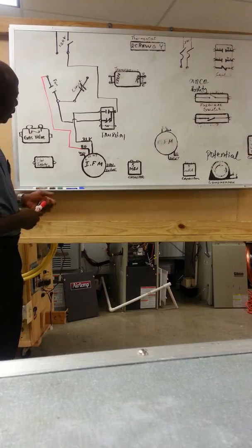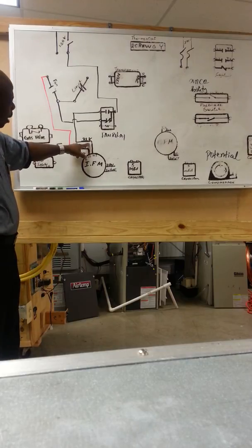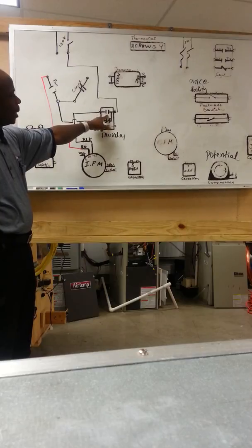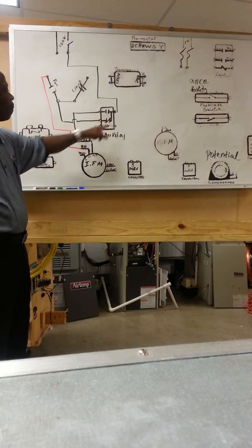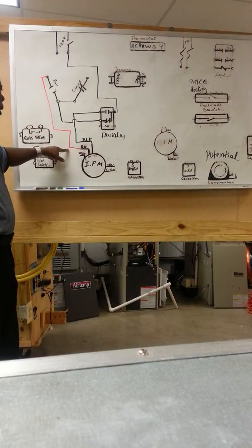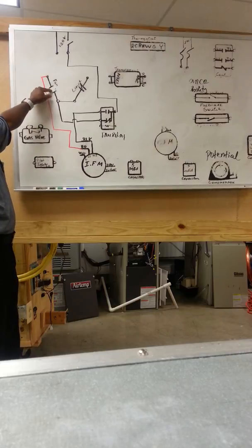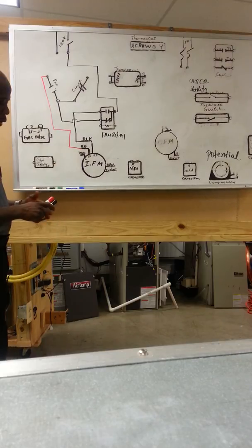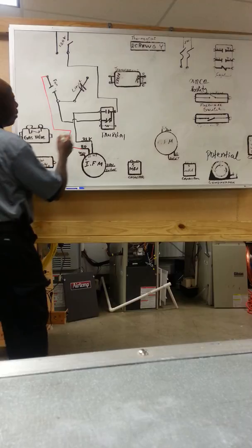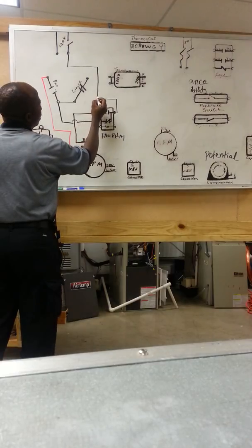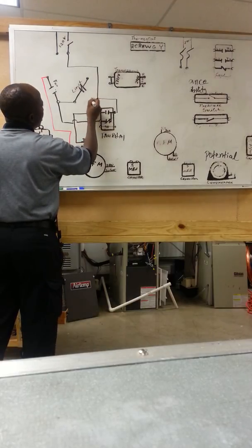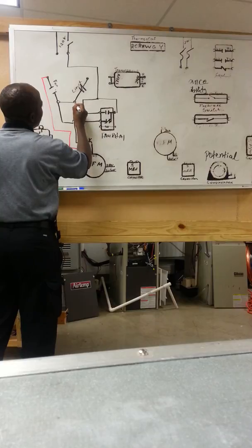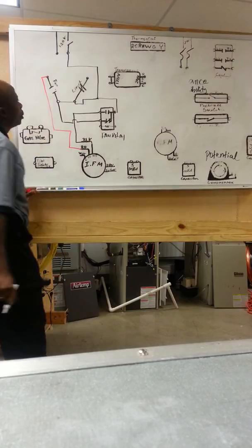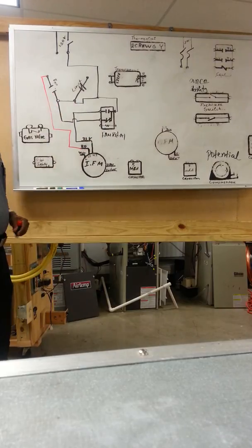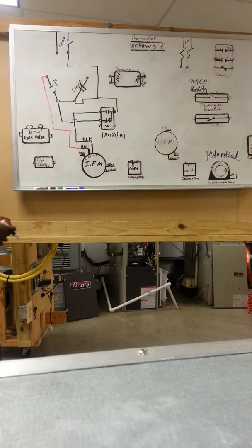But if you look at this right now, the high speed, which is the black wire, is coming straight from the fan relay, but it's coming from the normally open side. The red wire, which is the low speed, is coming from the fan center, also from the normally open side. So now we're going to get power from here, the main power, and send this power down to the fan center. Now the limit side has power.